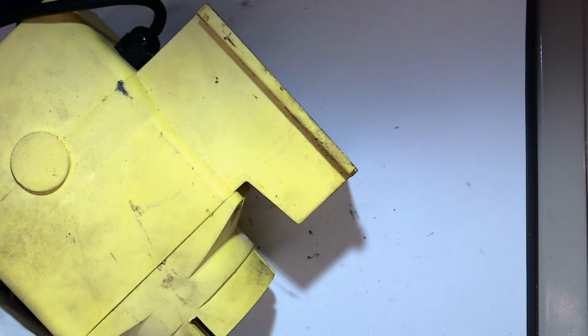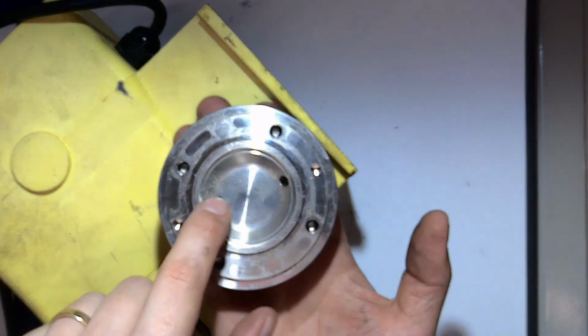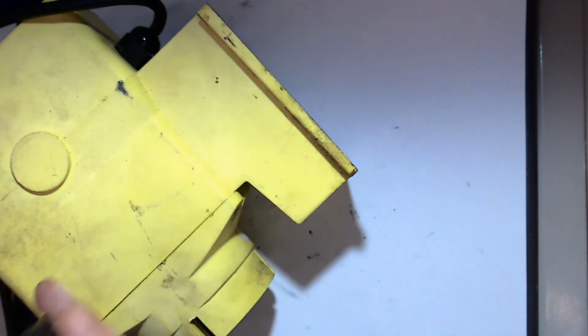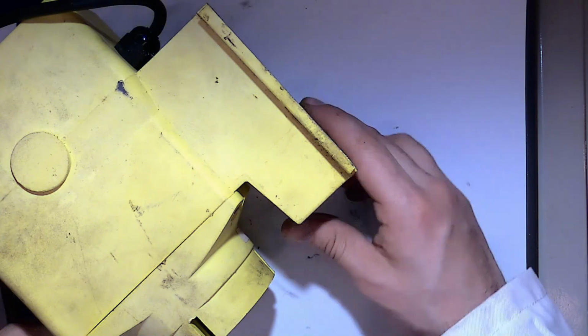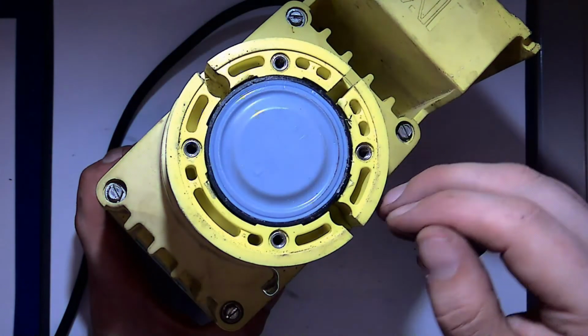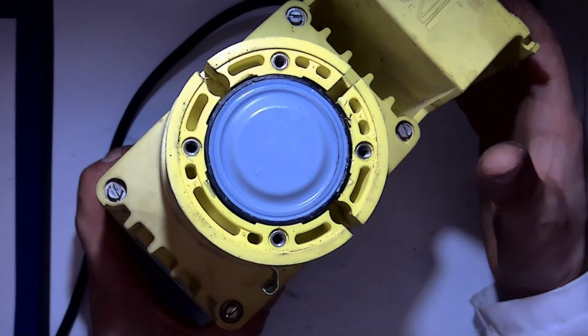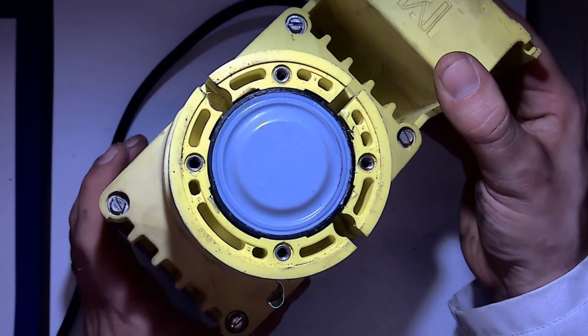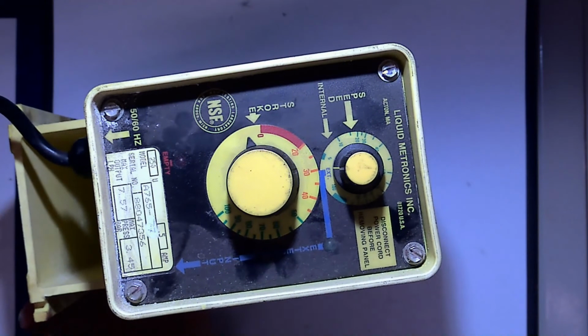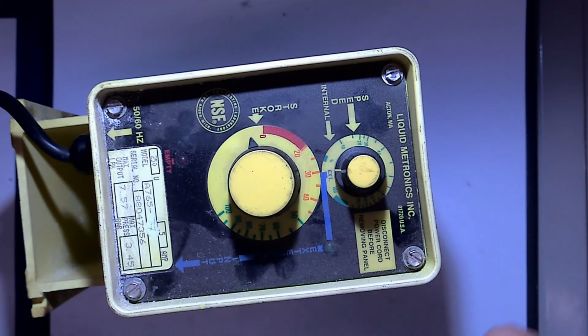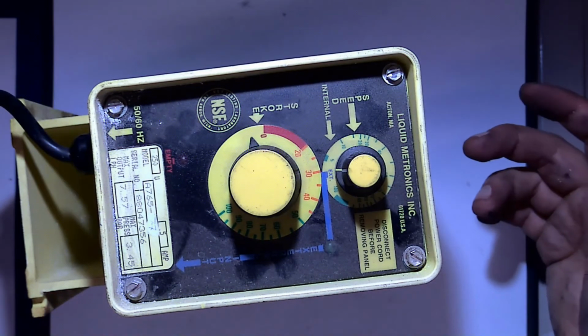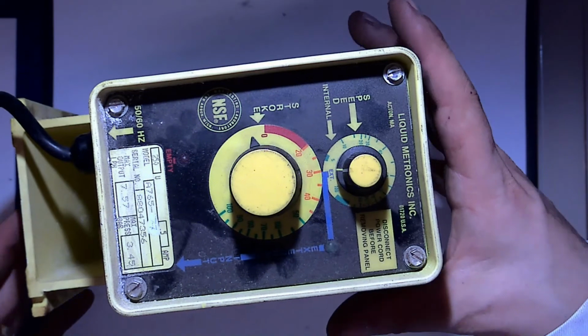So there we go. There's the head, again, 2 at the bottom, 1 at the top, fluid's flowing that way. There's the diaphragm component. Goes in and out, which forms that vacuum and that pushing pressure inside the head and creates the fluid flow. Okay, briefly mentioned, on the back there's your control panel, so your speed and your stroke. These can also be sort of remotely computer controlled, where, you know, if the fluid concentration drops below a certain point, it engages the pump, and vice versa. Okay, so that's the diaphragm style pumps.